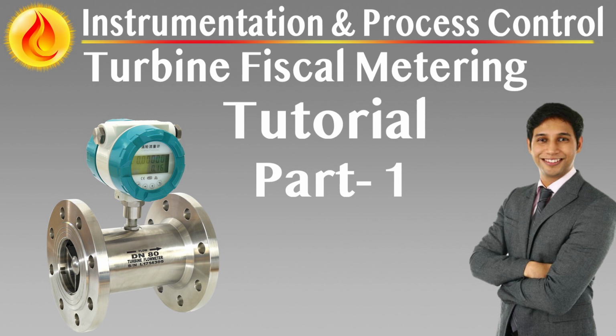Safety and thermal protection. Each metering run must be equipped with thermal relief valves to protect against pressure buildup from trapped liquid exposed to temperature rise. These valves discharge to a hazardous drain or flare system in compliance with site safety requirements.